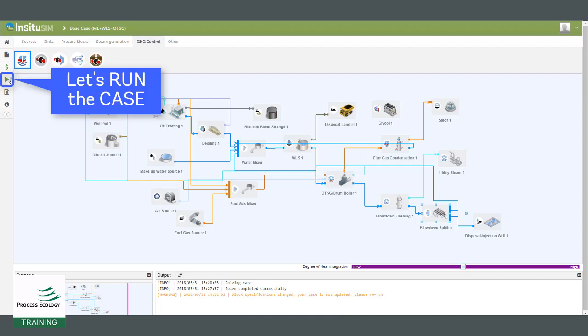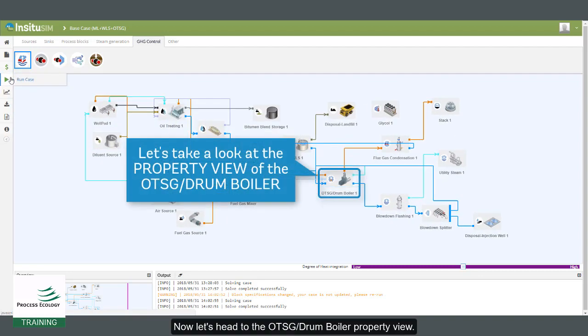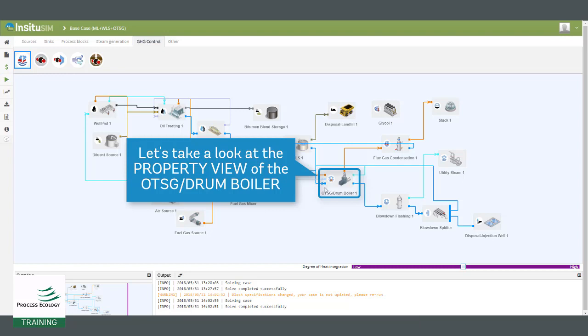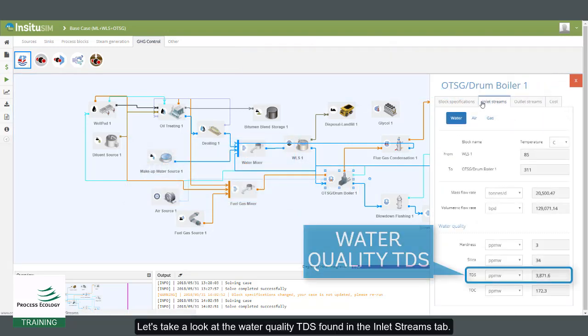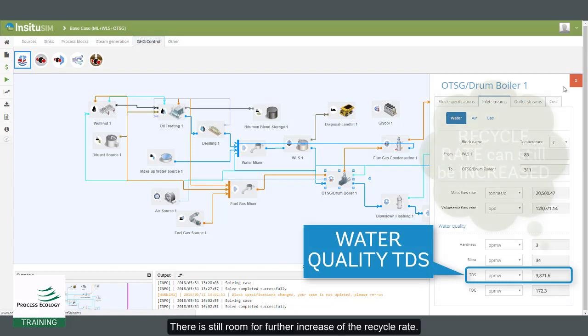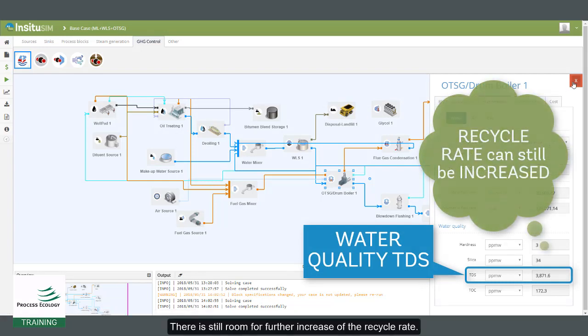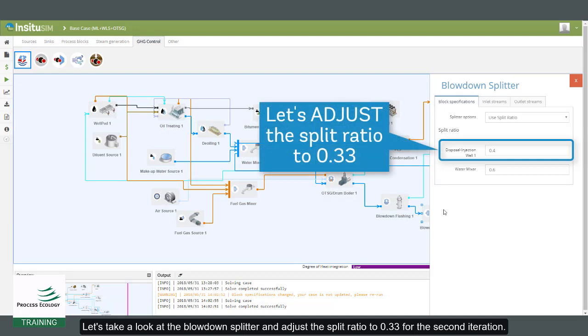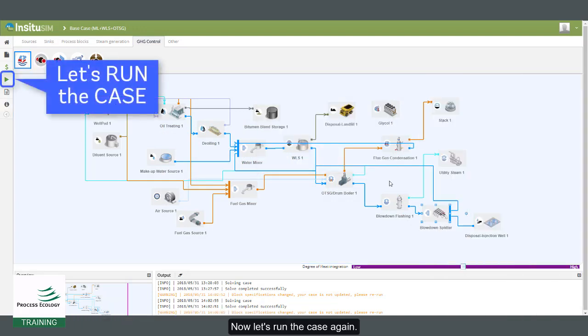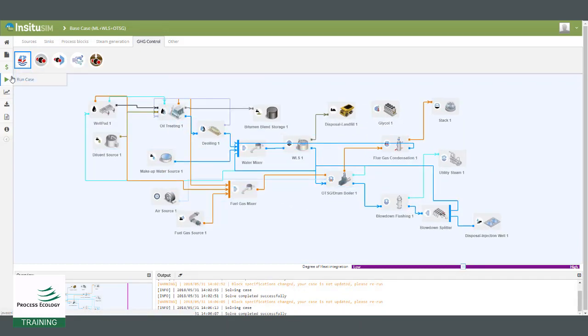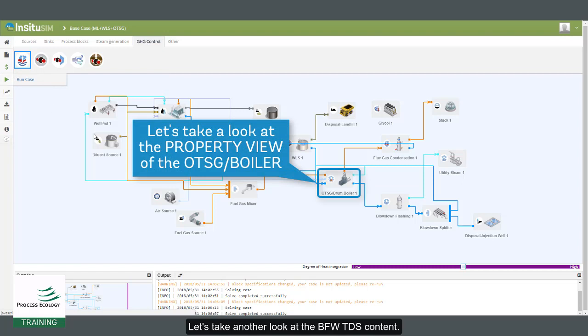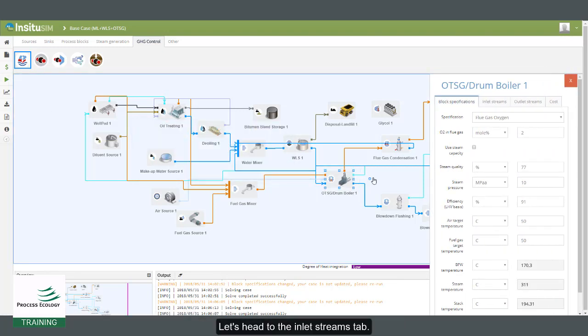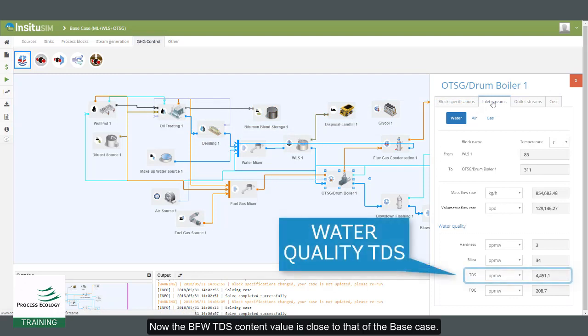Let's run the case. Now let's head to the OTSG drum boiler property view and take a look at the water quality TDS found in the inlet streams tab. There is still room for further increase of the recycle rate. Let's take a look at the blowdown splitter and adjust the split ratio to 0.33 for the second iteration. Now let's run the case again and take another look at the BFW TDS content. Now the BFW TDS content value is close to that of the base case.